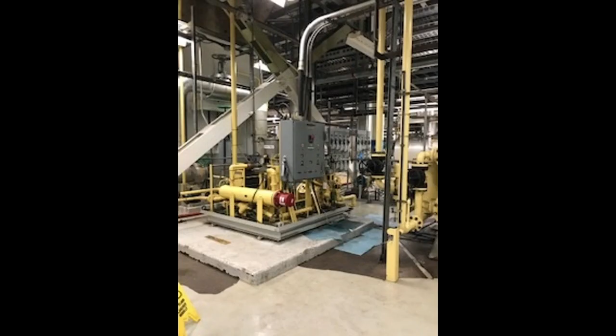This next piece of equipment is the turbine oil purifier, and it's really important that our turbine oil is as pure as possible. Any impurity, whether it's water or some sort of particulate, can trip the turbine or damage the blades. And so this oil purifier is taking out, it's like a centrifugal force, taking out the water. And we're actually checking this one more than once a shift because it's so important that we're collecting all of those impurities.